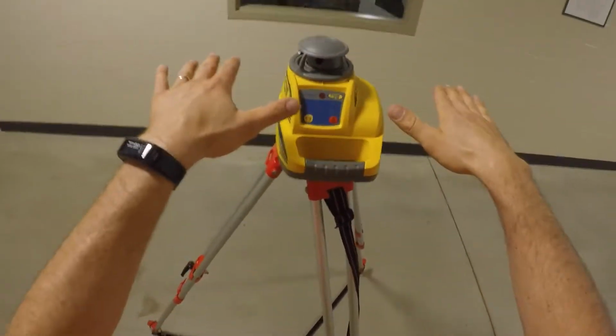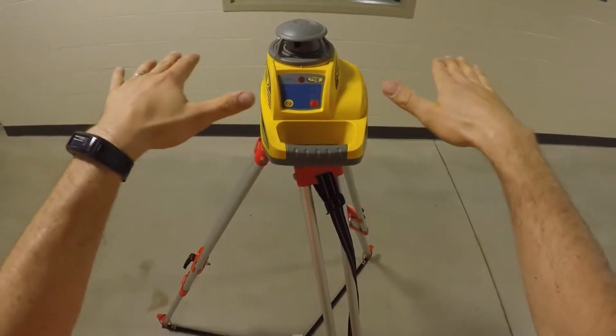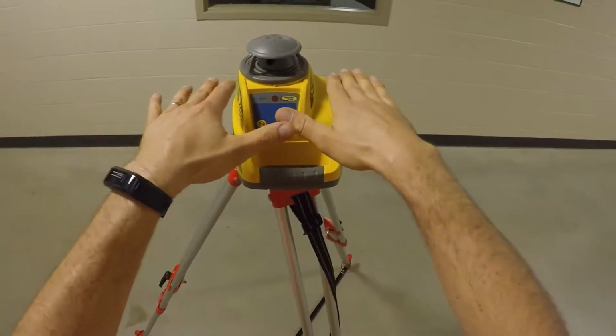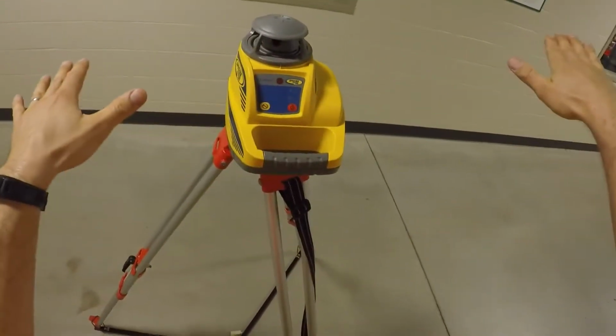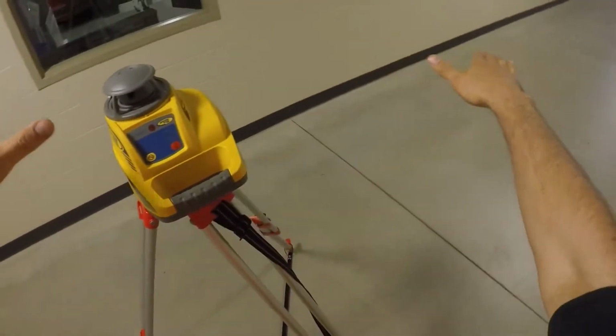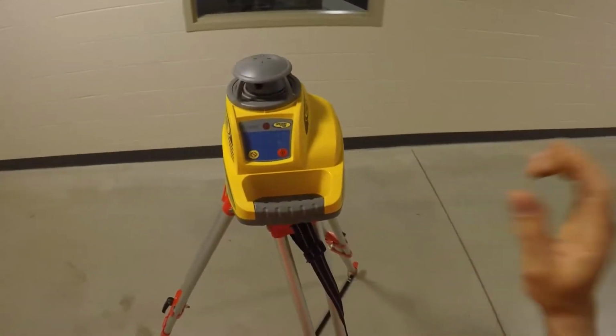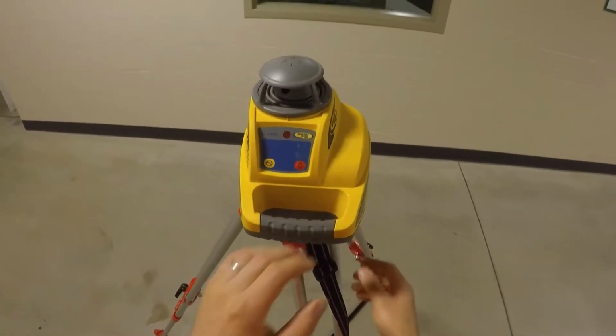So this laser is rotating about a plane, and obviously we want to make sure it's level. So when we point it, if it's off in space, kind of tilted, it'll give us a high mark, and then when I rotate the instrument and do it again, it'll give me a low mark, and I'll see the difference between the two and know I'm off. But if it's ideal and it's within calibration, we won't be off.